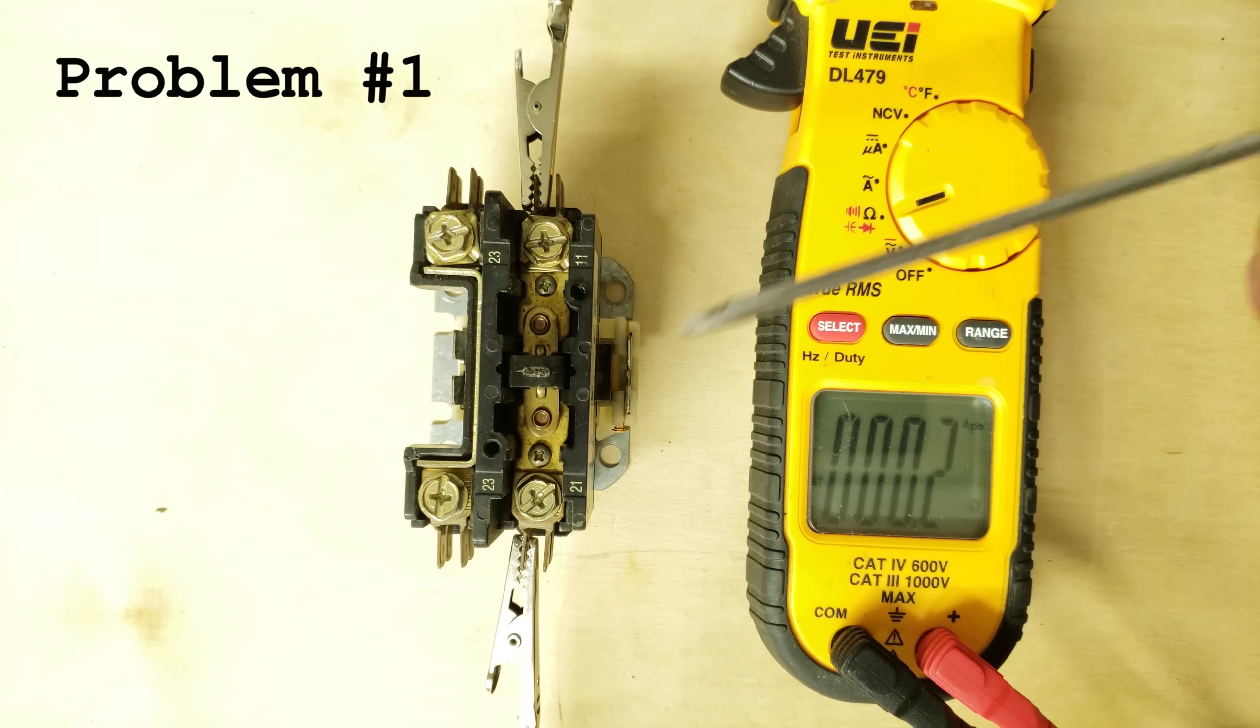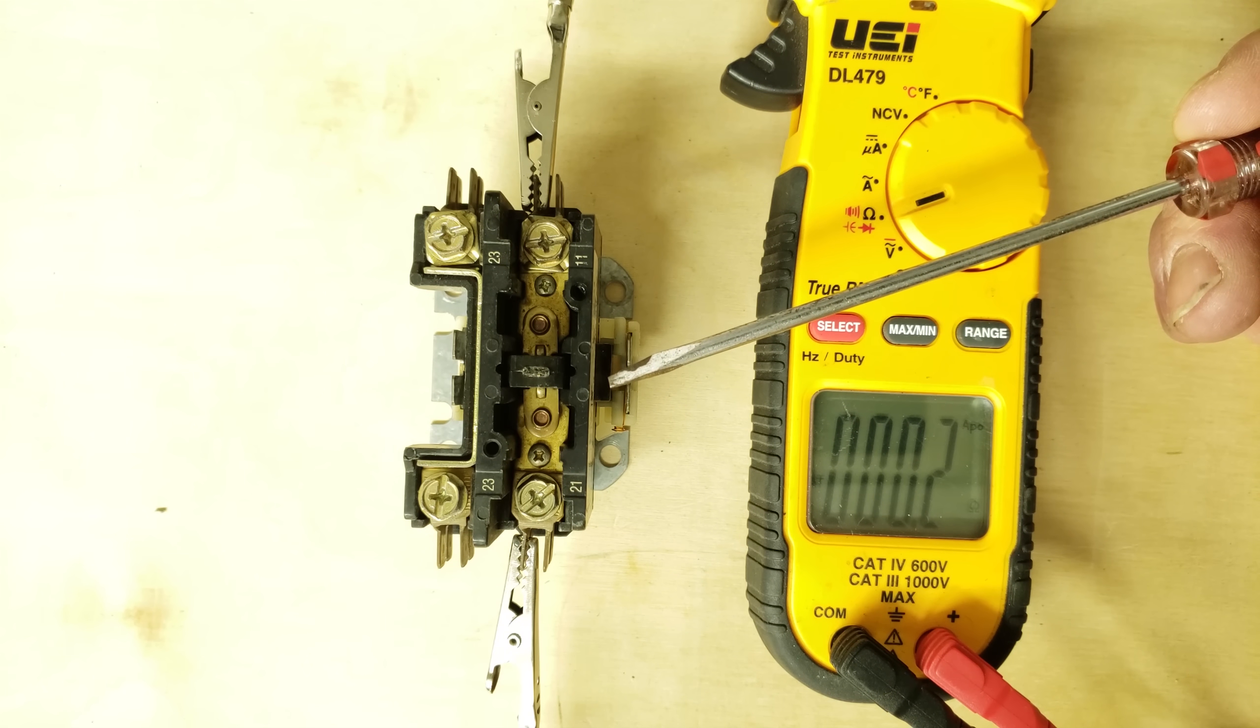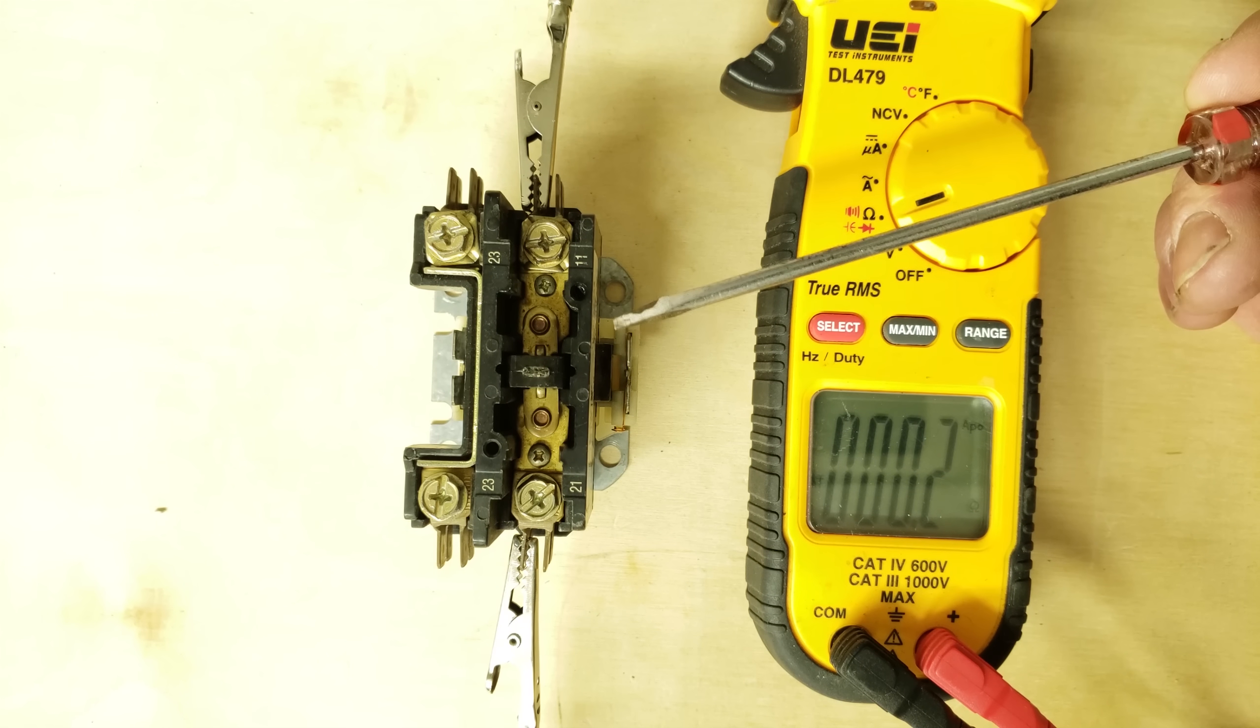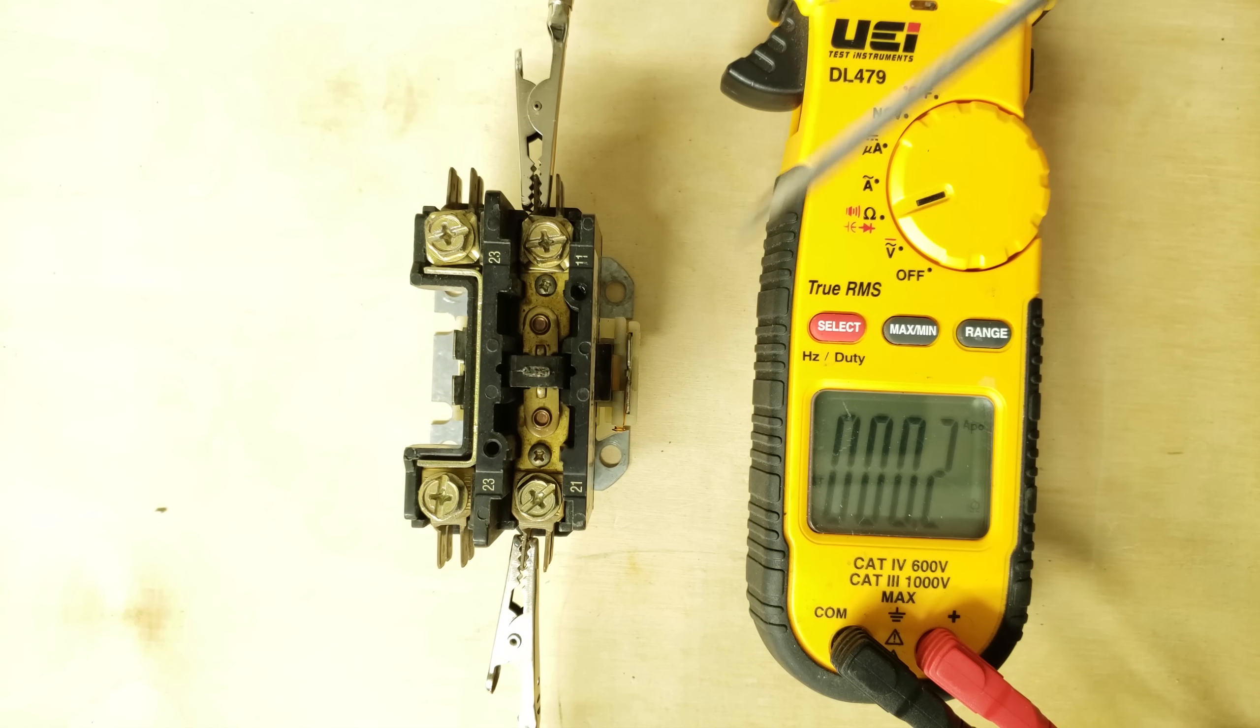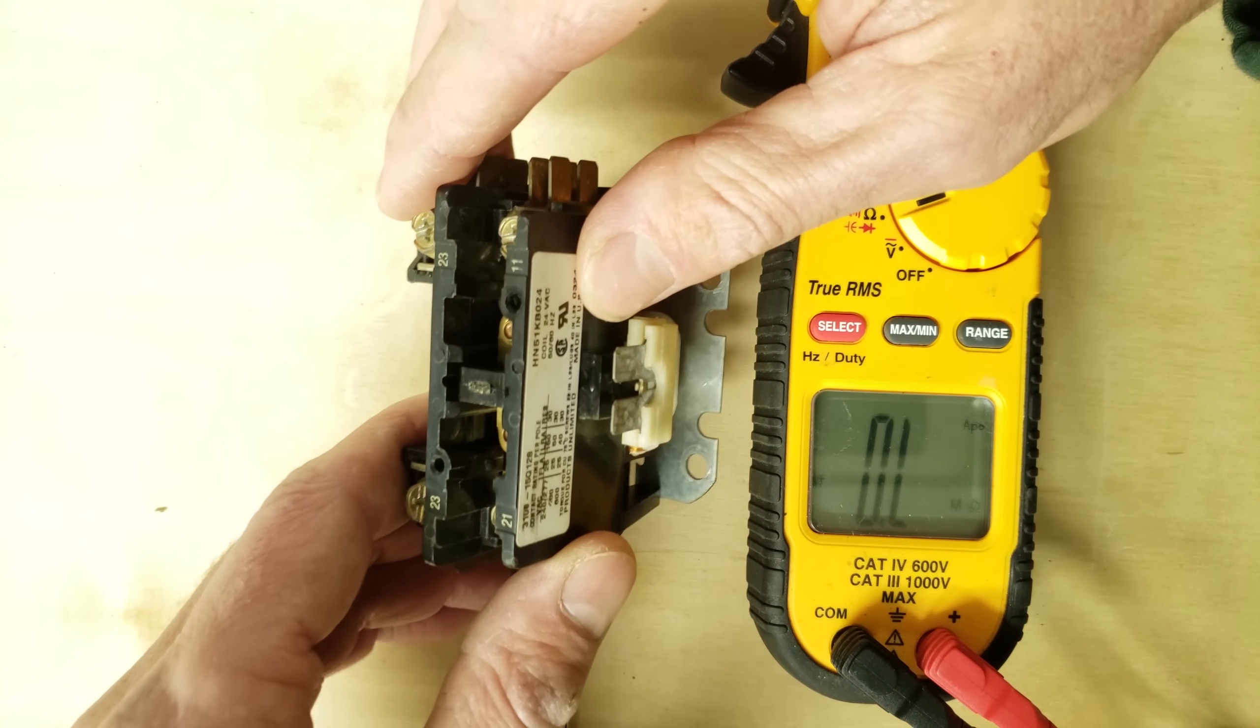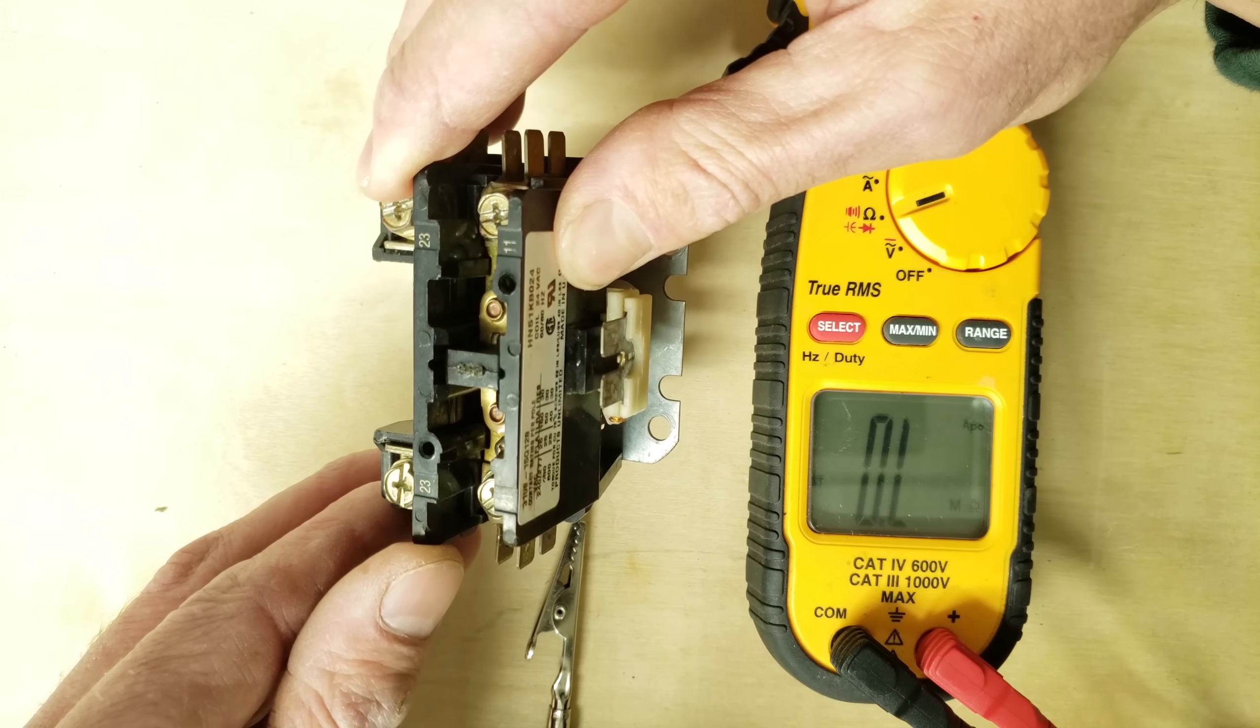Problem number one is when the contactor is stuck in the closed position and this happens when the contacts are welded together just due to high amperage. They melted and fused together and you see we're reading 0.2 ohms across this contactor. It is in the closed position even when we don't have any 24 volts on the side. You can see the contactor is actually stuck in that closed position.